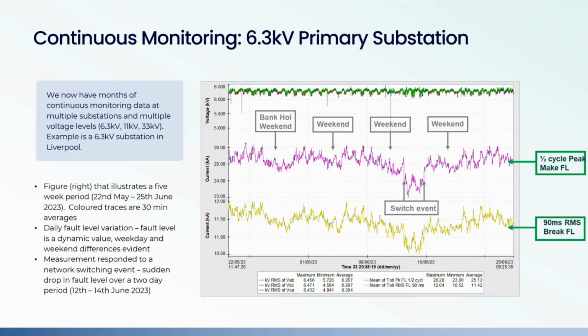So again, this is really opening doors, and we could see fault level as a dynamic value. Operationally, for example, the control room might decide that if they're worried about fault level and they want to do some switching, if they know from trends that the fault level is lower at nighttime or lower at the weekend, they can potentially schedule the switching for those times instead.